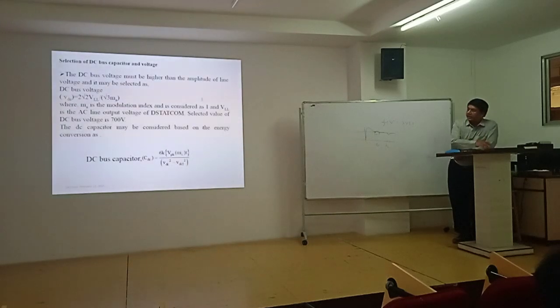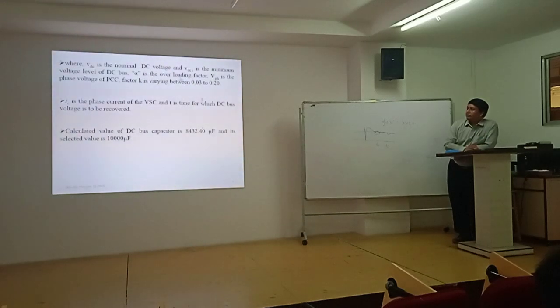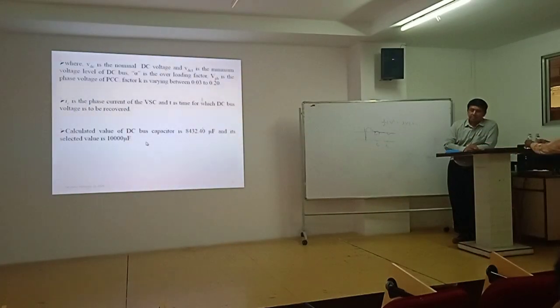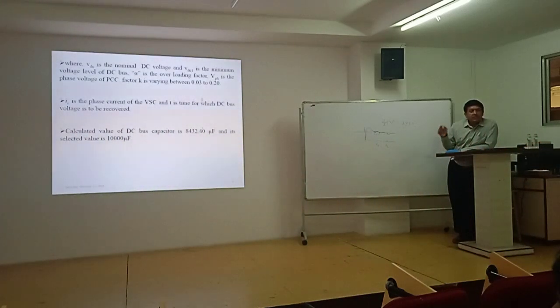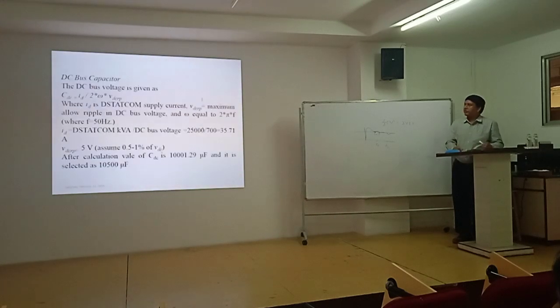Or by this formula also we can design. After designing, the value of CDC we have to observe: 8432.40 microfarad, the round figure 10,000 we can take. This is by formula. By the basic guideline, for each 5 kVAr, here we have to take 25 kVAr, so for each 5 kVAr we have to take 2000 microfarad. By this formula also we can design.